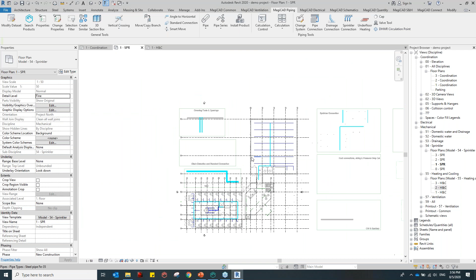Let me show you the standards we follow for sprinkler calculation. When you want to do a sprinkler calculation, make sure your design area is defined - there's a control and a sprinkler design area. For example, my design area is test 1 - I put in test 1, the height of the area, the sprinkler category, and the hazard category, such as ordinary hazard, OH1, OH2, anything.